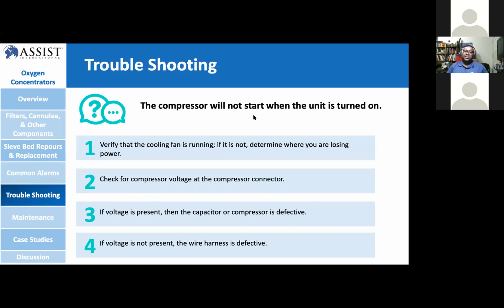So if the compressor will not start when the unit is turned on, verify whether the cooling fan is running or not. If not, check the power line. Maybe there's something wrong with the connection. And check the fuse, whether it's in good condition or not. Then check the compressor voltage and compressor connection. Very important. If the voltage is there, maybe the starter capacitor is not working properly or the compressor is defective. If the voltage is not present on the wire harness, maybe the cables are not working properly or are broken.